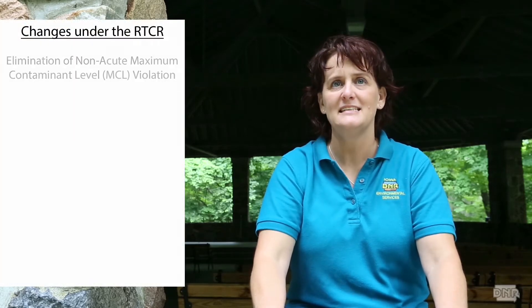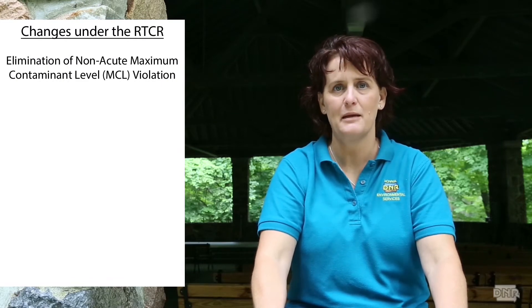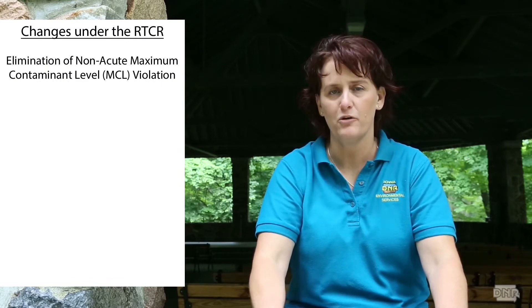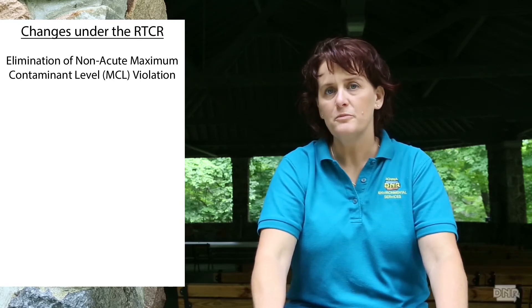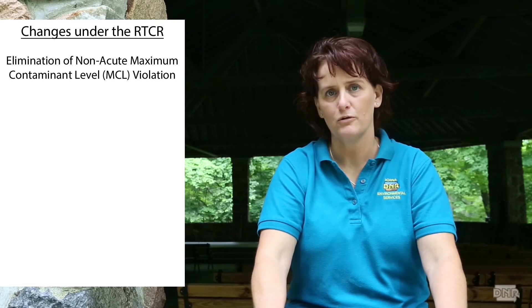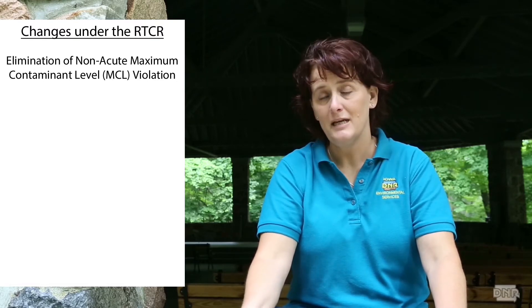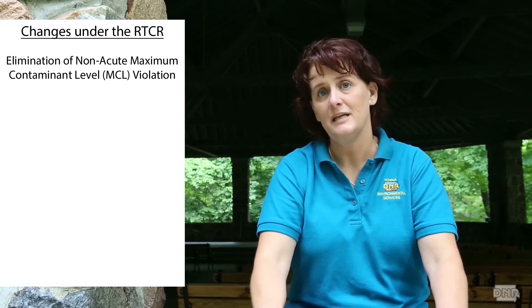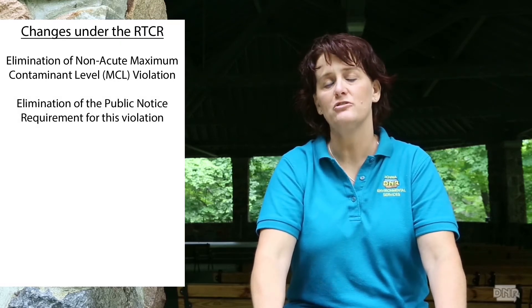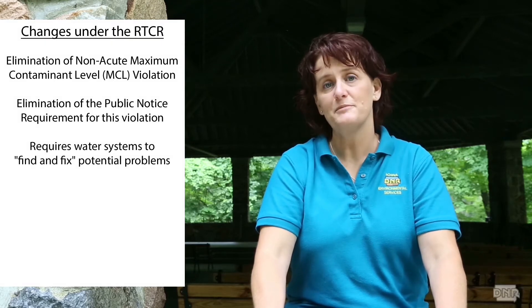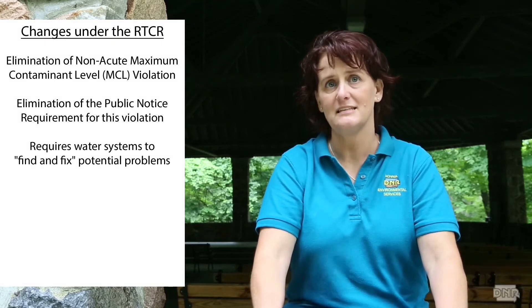As you probably guessed, the revised Total Coliform Rule has made a few changes to the original rule. One of the biggest changes under the RTCR is the elimination of the old non-acute maximum contaminant level violation — you might know it better as a non-acute MCL. This is the violation that was issued when multiple sample results showed the presence of total coliform bacteria. Since this rule eliminated the violation, it also eliminated the need to do public notice. Instead, the RTCR now has you look over your water system and attempt to find and correct any issues that might be causing the contamination.